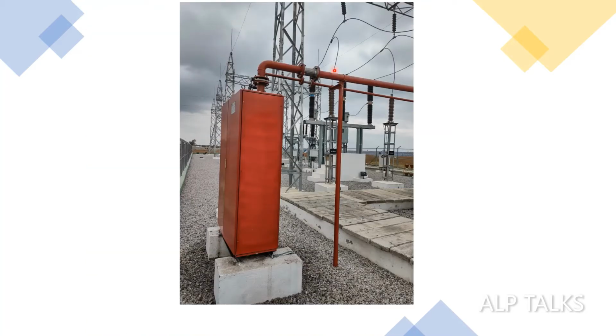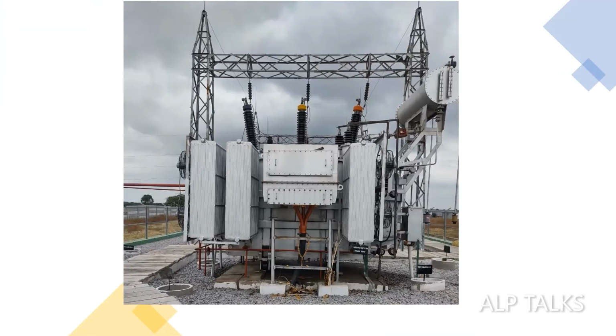This is NIPS system. Generally, some good companies in India offer NIPS systems for the substations. NIPS is nitrogen injected fire protection system. This is a transformer HV side view, the 33 kV side view. So we have cable here. These cables are coming from the ring main unit, the output of all the inverter duty transformers together. So this is the structural arrangement.